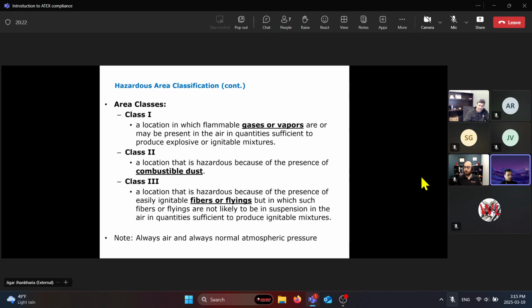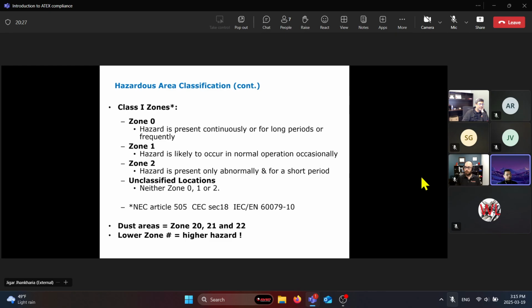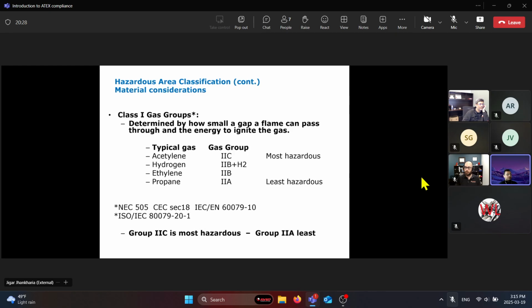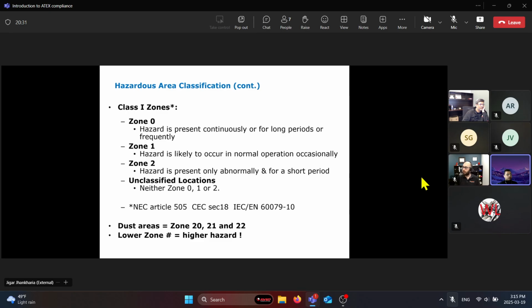That's the basics of the classes, and then we get into the zones and divisions. Division 1 is pretty much the same as Zone 0, where a hazard is present continuously, for long periods of time, or frequently in the classified area. Division 2 is the same as Zone 2, where a hazard is present only abnormally or only for a short period of time. In the past, the North American classification was Division 1 and 2.